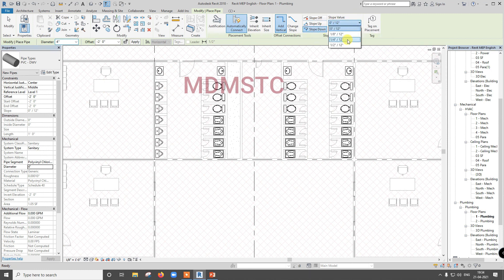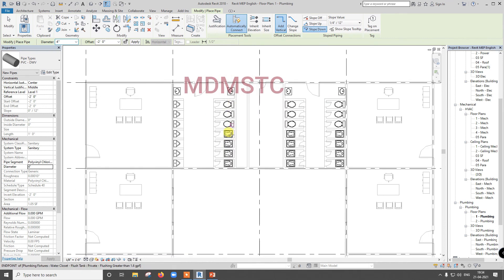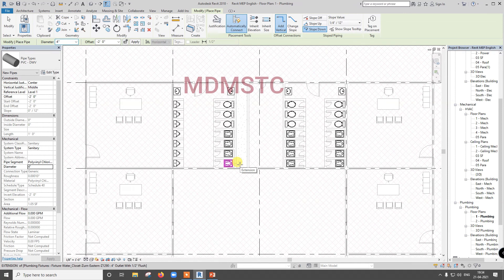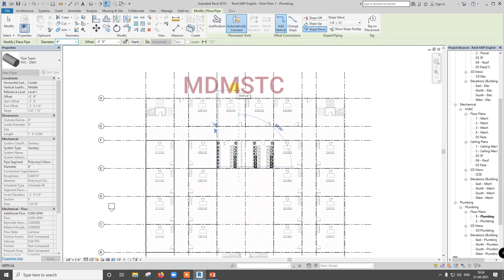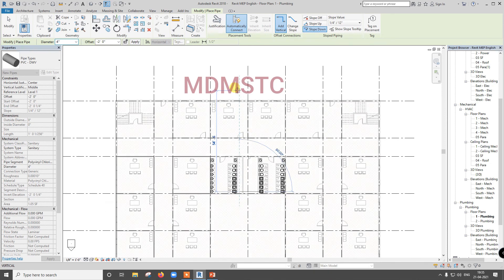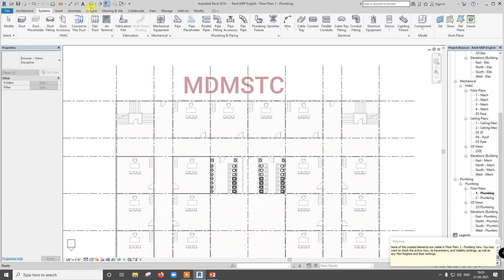We will select slope down and enter the slope value — preferably quarter inch or half an inch is preferred, so I am going to select quarter inch. I am going to bring this and connect from here to outside directly, because an important thing is that your drainage pipe should leave the building at the shortest distance. Click escape — but we are in plumbing only, but we are not seeing any pipe connection. Let us check here — piping connection is there.